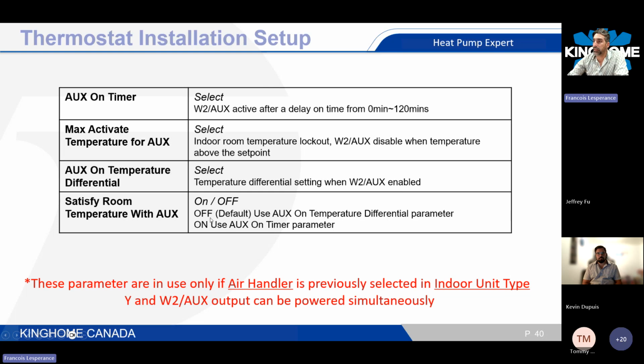Satisfy room temperature with aux. This is where you have to have a good understanding of this one. By default, it's going to be off. This is just a sliding on-off button. It will be gray, so default off. We use aux on temperature differential. So it's aux on timer or aux on temperature differential. It's just one or the other. You can adjust both, but you can choose only one to run during that period. So if you put it off, we're going to use the temperature differential. If you put it on, then you disable that one to activate the timer that you have set already.